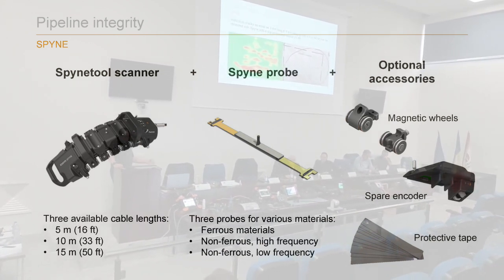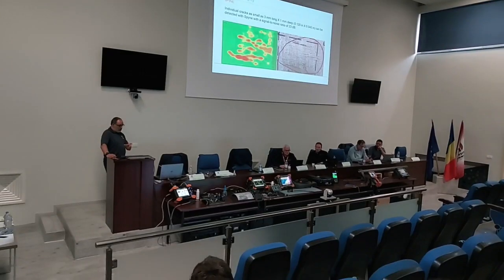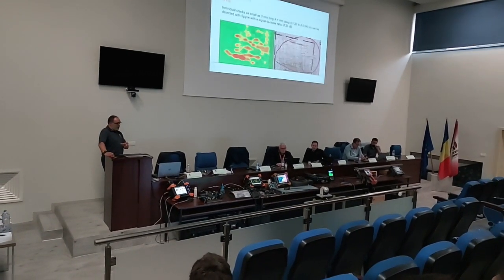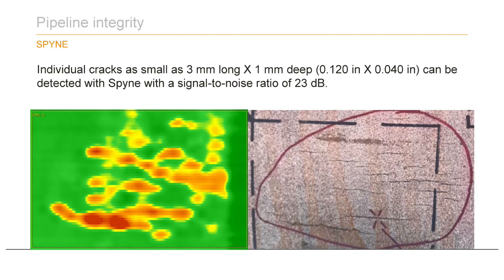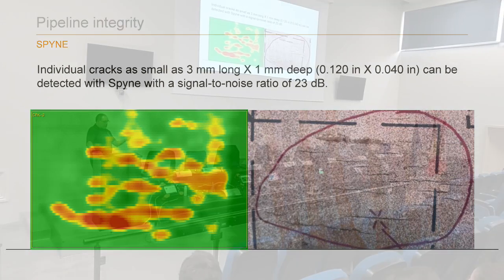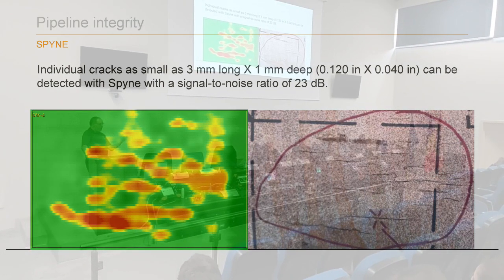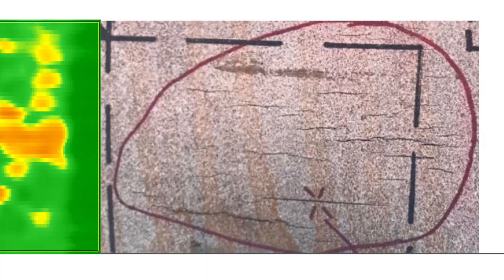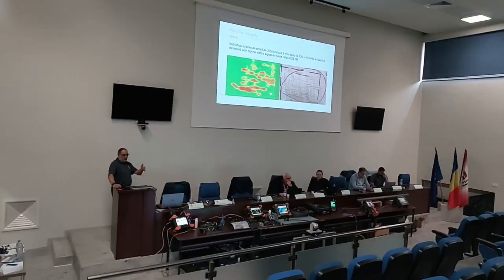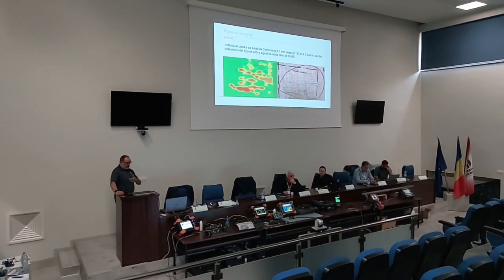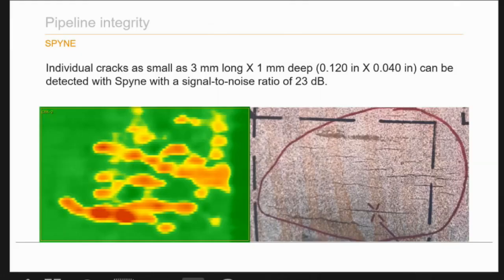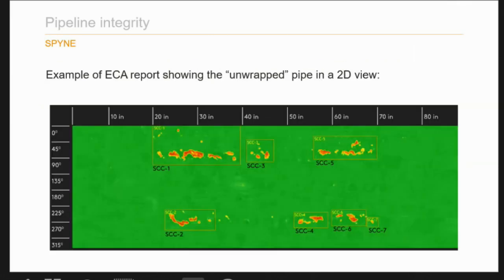A comparison between a real colony of stress corrosion cracking on the right with MPI and the signal you get on the left with eddy current array. On the right, you need to remove the coating, and eventually prepare the surface by sandblasting, then do the MPI. Depending on the orientation of the defect, you have to do your inspection accordingly, whether it's a longitudinal or transversal crack. With ECA, you have nothing to do, and even with some coating, you can still do the inspection and get the same results.